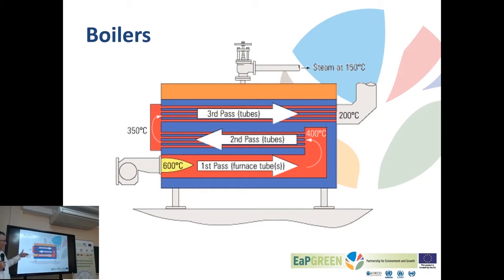Obviously, if the ratio of air to fuel is not optimized, this might be a source of losses. If I have not enough air, combustion will be incomplete. Result will be soot depositing on the pipes, increasing resistance to heat transfer, inducing higher exhaust gas losses. Scaling on the tubes might be an issue. If the water is too hard, the hardness will precipitate on the tubes, will increase heat resistance, will increase losses.